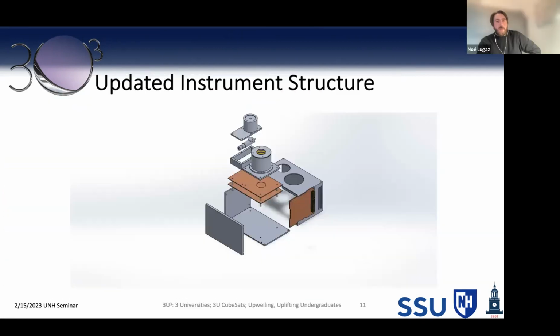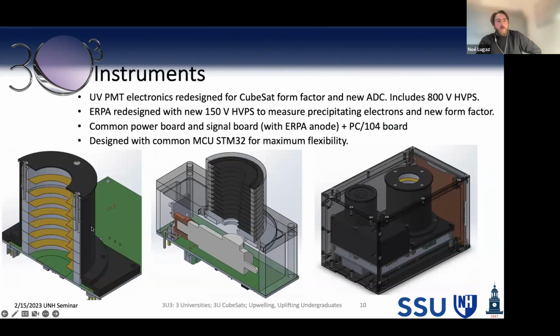Yeah, so the electrons are direct — I didn't spend too much time on the instrument, but it's an energy ARPA design. We put a bias voltage on some plates so that only some electrons get through. We step through 6 voltages every 125 milliseconds or so, if I remember correctly, directly measuring electrons. The top voltage is 150 volts, so we measure electrons between roughly 10 and 150 electron-volts.